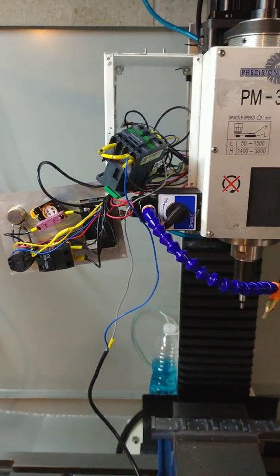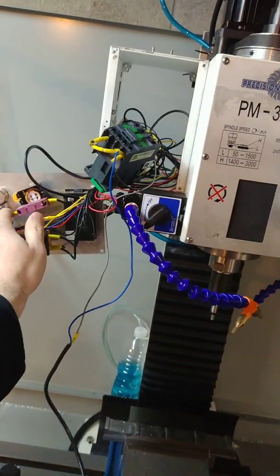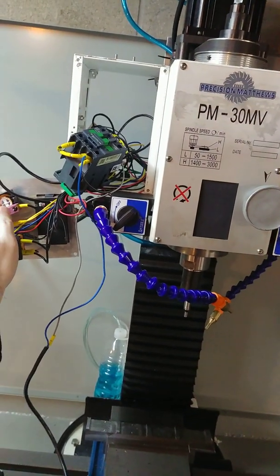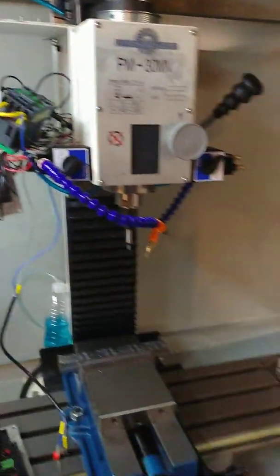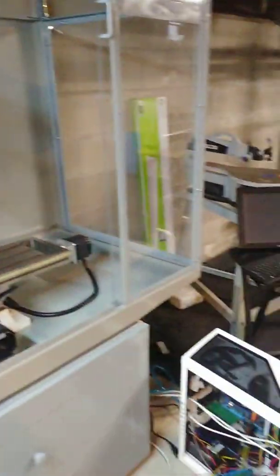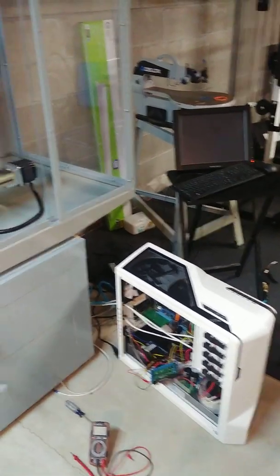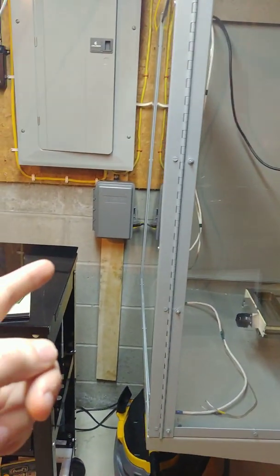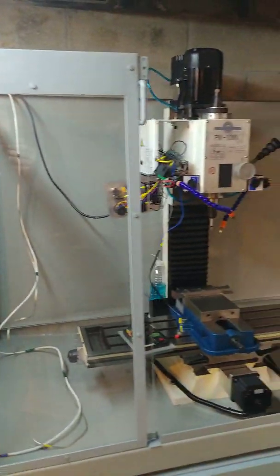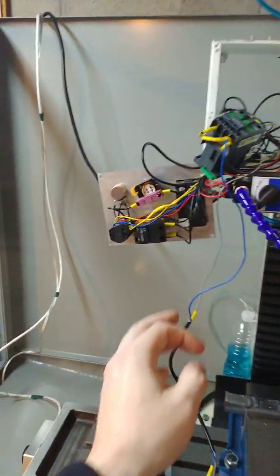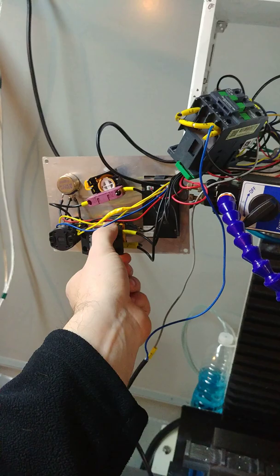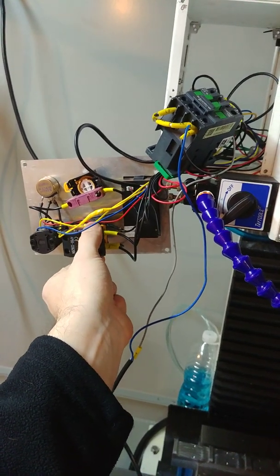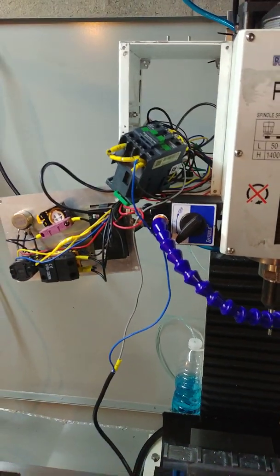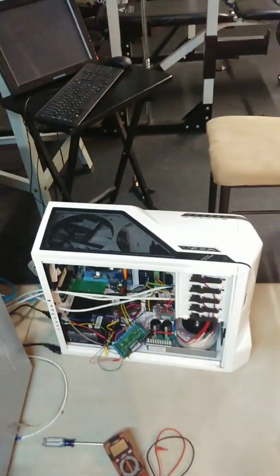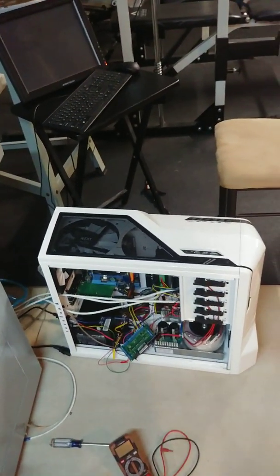So I hooked up the two lines to my wiper and my ground taps. I turned the computer on. I had no issues there. Got the controller booted up, and then flipped my 220 volt disconnect. The second I hit the green button on the front here, which supplies power to the motor controller and everything, I heard a loud pop. A flash of light came out of this controller or the computer, and everything turned off.